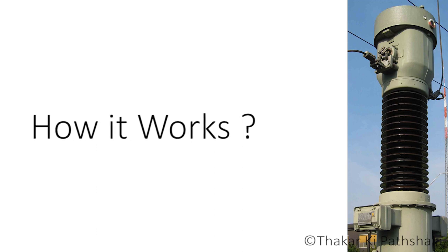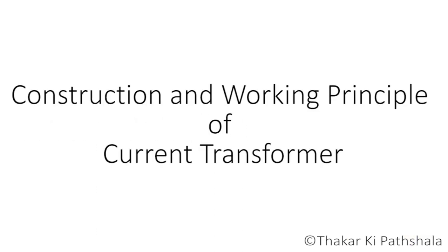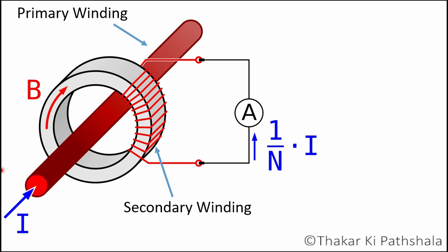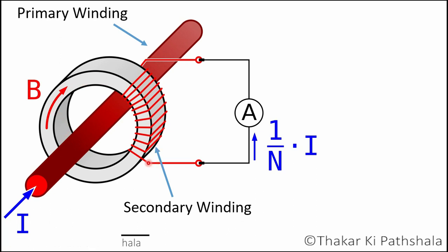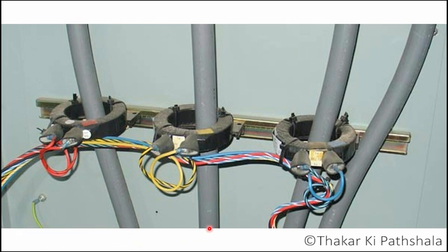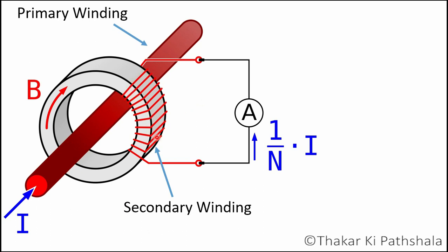Now let's look at the construction and principle on which a current transformer works. As shown in this figure, the general construction is similar to any other transformer — it also consists of two windings: primary and secondary. It transfers energy from one side to another with a suitable change in the level of current or voltage. The primary winding consists of one or more turns of wire of heavy cross-sectional area. In some cases the bar carrying high current may act as the primary. The primary is connected in series with the line carrying high current. The secondary is made up of a large number of turns of fine wire with small cross-sectional area, and is usually rated for 5 amperes.